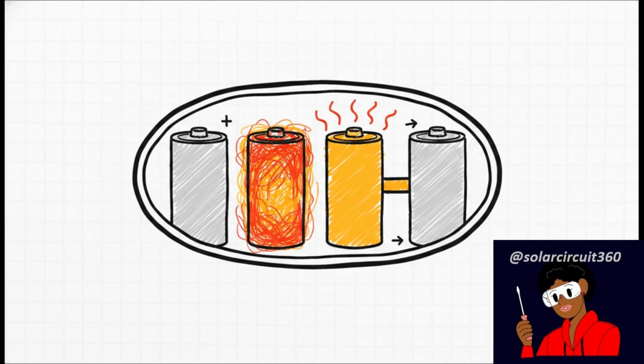And you know what? There's actually a super clever shortcut for this: thermal inspection. Since power loss to internal resistance turns straight into heat, high resistance literally makes failing parts hot. If you've got a thermal camera, just point it at your battery bank while it's discharging under a heavy load. It's like magic. It makes invisible electrical failures completely visible. You'll instantly see bad internal cell groups glowing warm, or spot loose terminals, corroded lugs, and failing bus bars way before they turn into a serious fire hazard.